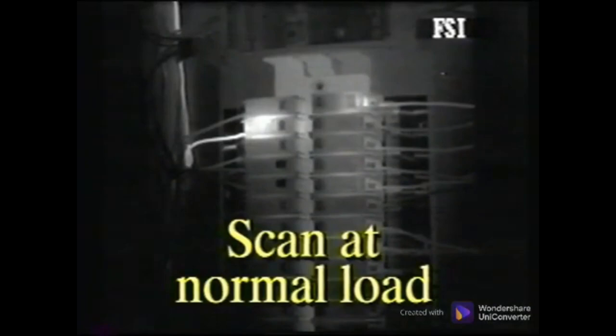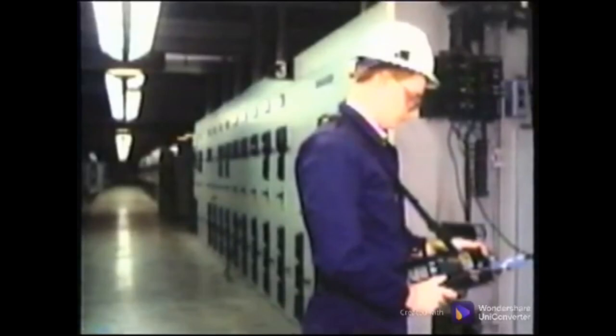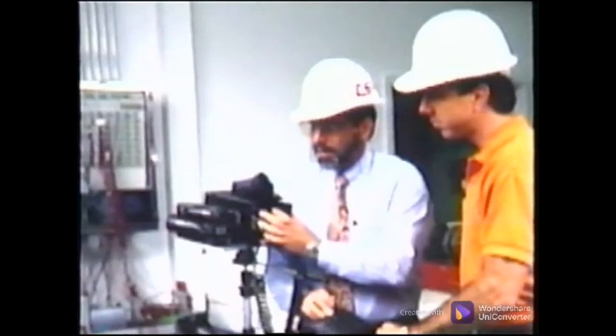When scanning closed panels, some may appear to be hotter than others. But remember that you are to determine the source of heat. Is this really radiated heat, or could it be reflected heat? If you can visibly see a bright spot or reflection, it will cause a thermal pattern. Is the heat from the cover itself, or has it become hot due to conduction or convection of internal heat? Have qualified personnel open the box for better inspection.